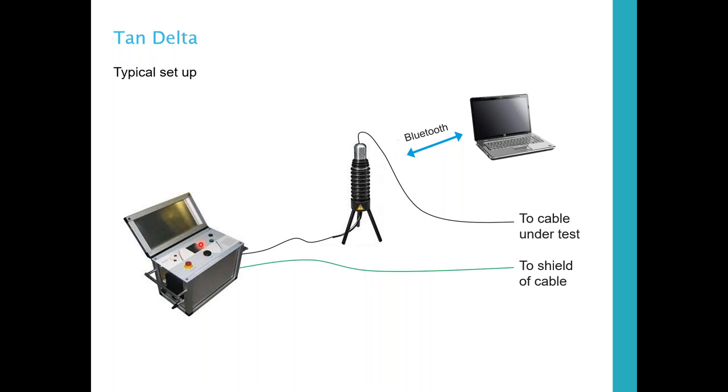Size-wise, all that, it just doesn't give you as much capability as the VLF does in means of location, in means of seeing what your inception and your extinguish voltages are. Which is one of the reasons the VLF is a more common test now, it's similar equipment, but it gives you more data and gives you the ability to get a better feeling for what the condition of your cables are.